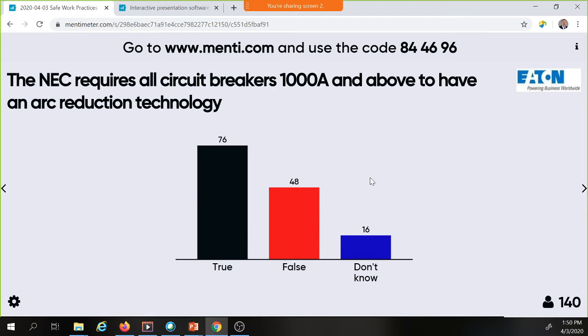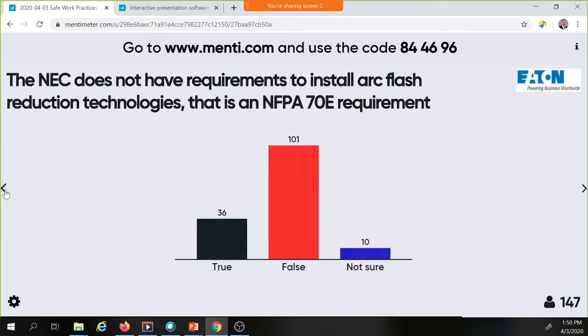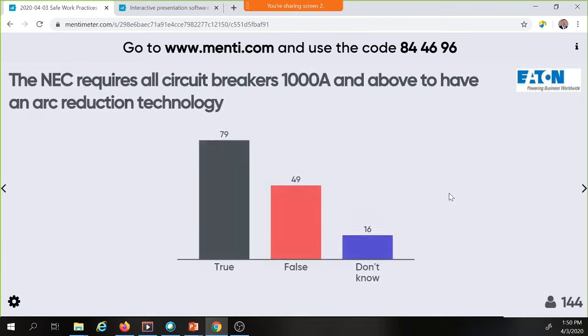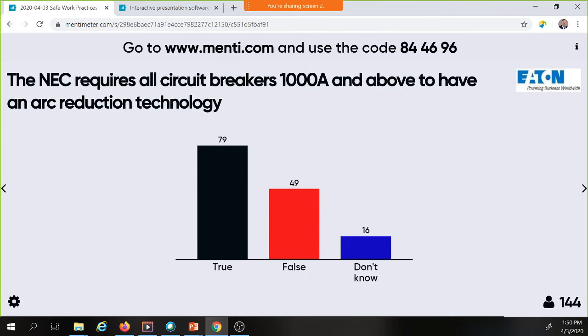The NEC requires all circuit breakers 1,000 amps and above to have an arc reduction technology. Okay, let's think about this one. You 79 said true. Now hold on, let's take a look. Wait, let's go back. NEC does not have requirements. Okay, so it's only 36. We had 101 said false. All right, so 79 said true, but I threw you a curveball. The curveball was it's not 1,000 amps and above. It's 1,200 amps and above. You need to have an arc reduction technology, 1,200 amps and above. That is found in 240.87 and 240.67 of the National Electrical Code.